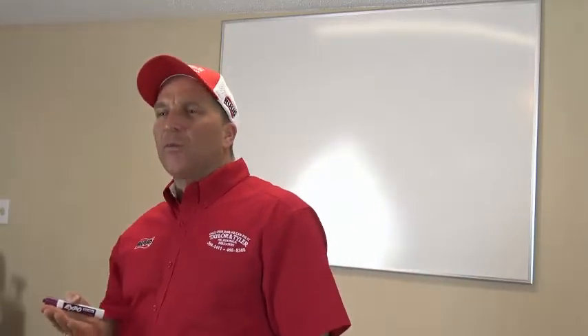It's not blowing. Okay? What's the difference between a blown fuse and a burned fuse? A burned fuse overheats. Okay? Because of heat. A blown fuse, over amps. So if you got a 30 amp fuse and you draw 60 amps on it, you may blow the fuse. But if you got a 30 amp fuse and you're drawing 28 amps, is it going to blow? No. It's not going to blow. You know what it's going to start doing? It's just going to start getting hot. Because the resistance is 30 amps. You're drawing 28 on it. It's going to start getting warm.